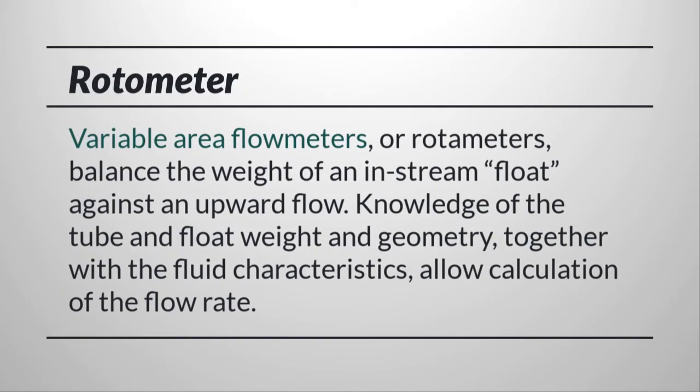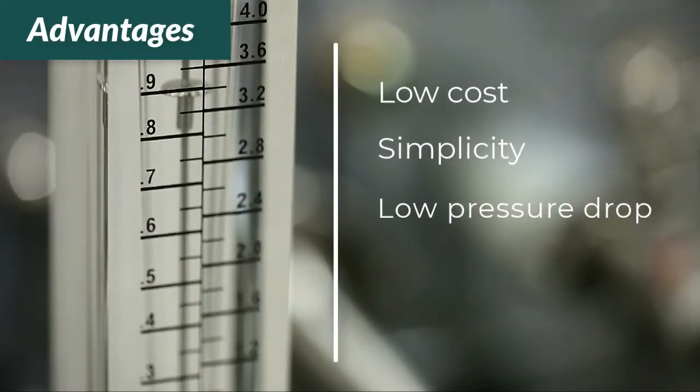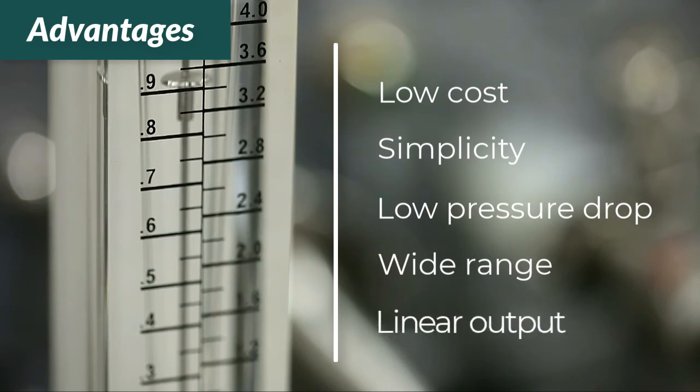In a rotameter or variable area meter, the force of the flowing fluid moves a weighted float upward in a tapered vertical tube. The higher the flow rate, the higher the float's equilibrium point. Advantages include low cost, simplicity, low pressure drop, wide range, and linear output.